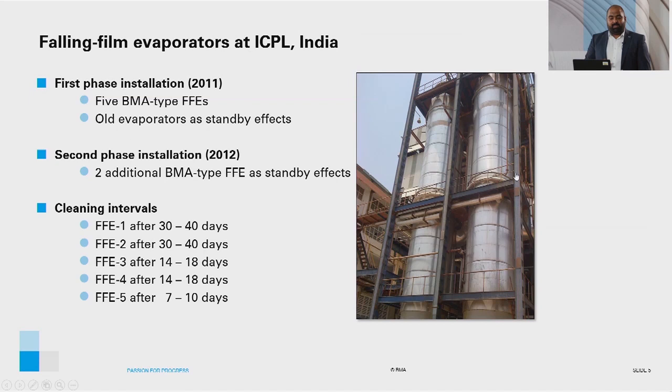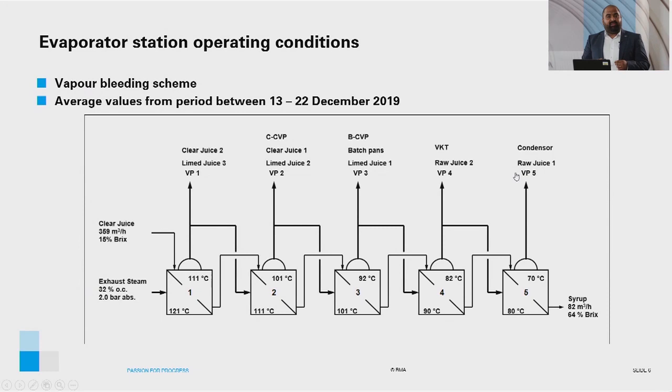The schematic diagram shows the vapour bleeding scheme and operating conditions of the evaporator station. Vapour from the later stages are used for raw juice heating. One key point in reducing exhaust steam consumption is the utilization of Vapour 4 for vertical continuous pan operation for high-grade massacute. The figures shown are average values from 13 to 22 December 2019 — for example, clear juice flow rate of 369 cubic meters per hour at 18 brix entering the first effect, and syrup flow rate of 82 cubic meters per hour at 64 brix leaving the last effect.